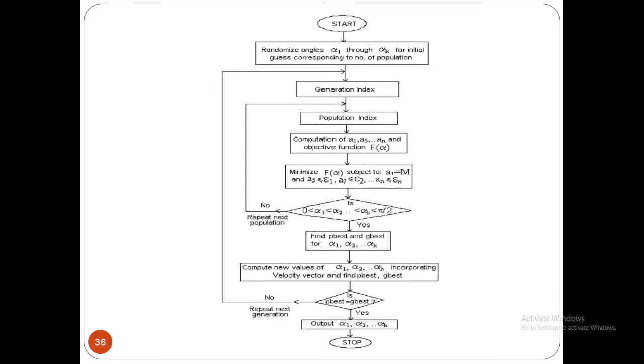This is one method. Same system, you go for this technique where you are restricting these individual harmonics 5th, 7th, 11th, 13th to 3%. You are limiting to 3%, not completely eliminating. And total harmonics, it should be less than 5%. You are minimizing the objective function to less than 5%.